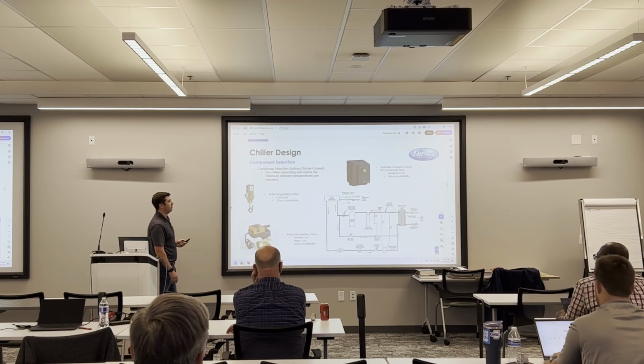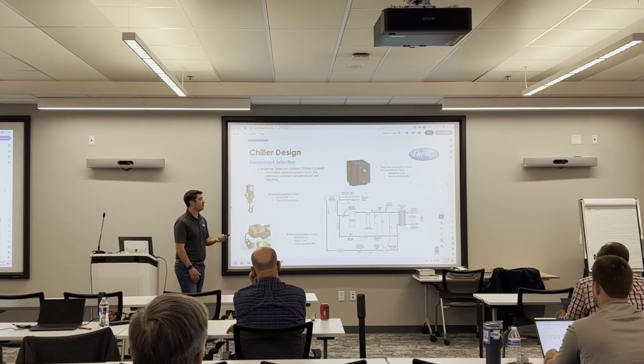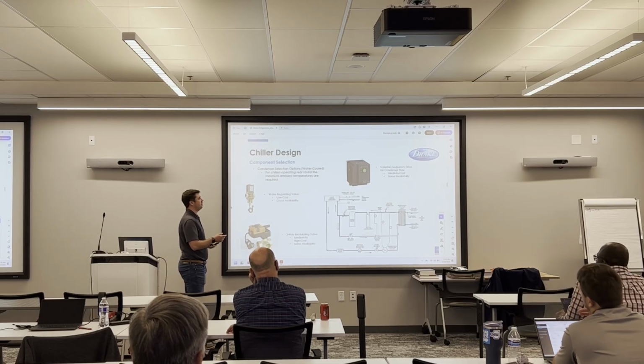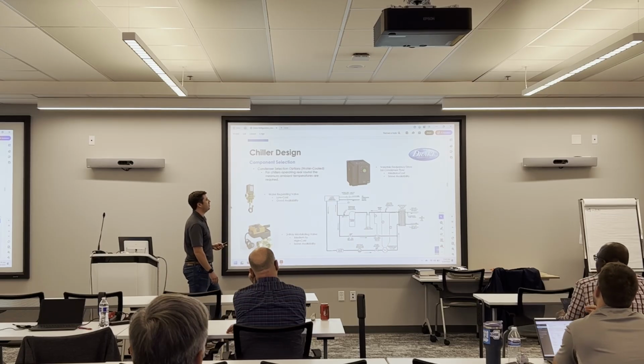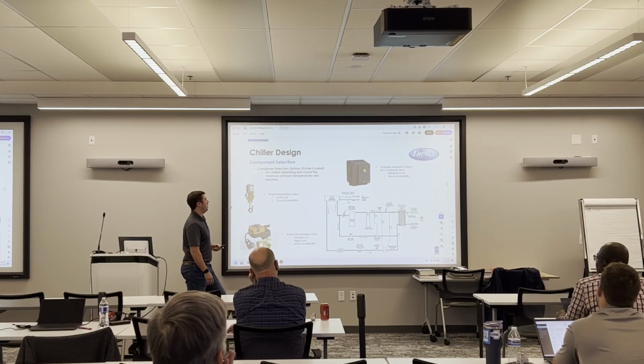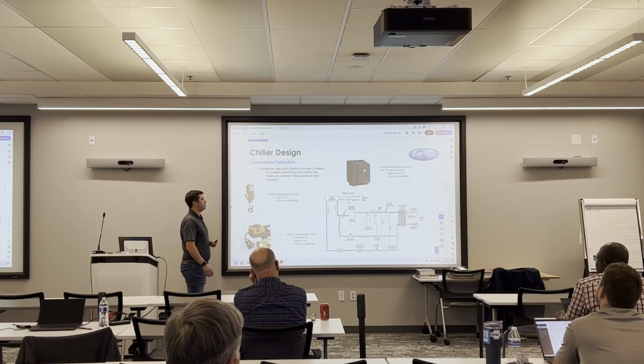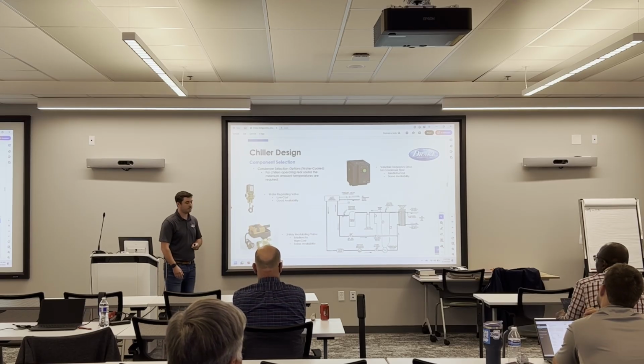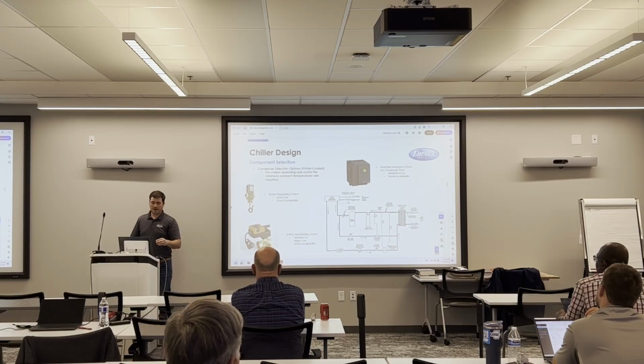And then the other option that I have up here is just a variable frequency drive for the condenser pump or condenser flow. So you have to imagine that you've got water flowing through this condenser at a specified flow rate. If it gets cold in the wintertime, you might not need as much flow, so what you can do with a variable frequency drive is slow down the speed of that flow and control an actual discharge pressure off the compressor. Medium cost, some availability. And there's a bunch of other options out there, but these are the ones I wanted to highlight just based off the fact that I've physically put them in chillers.